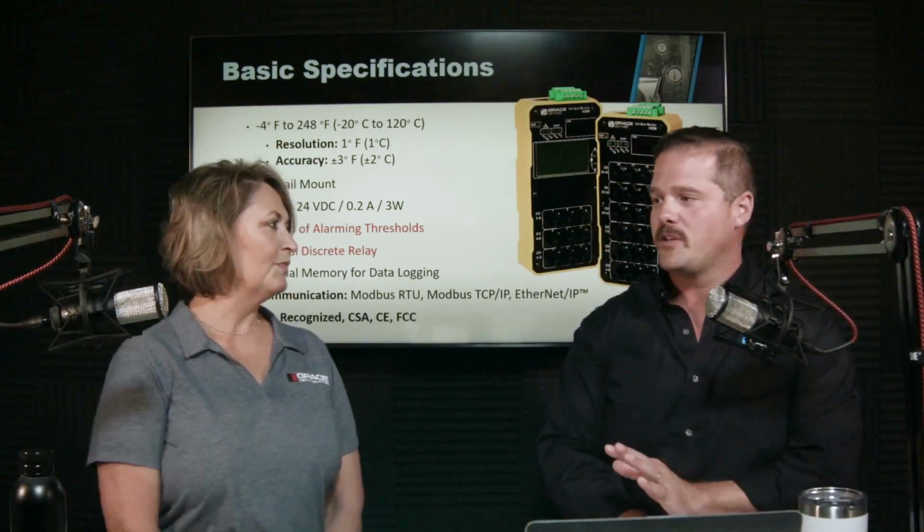I followed up with them, oh my gosh, did the product miss it? He goes, no, Drew, your guys' product performed just as intended. We were able to pull the data log from the charred remains of the switchgear. And sure enough, the data log showed increasing temperatures. If only they would have had the budget to integrate it into their alarming, their SCADA, their building management system, however you get those alarms today, it would have been really, really nice. So now, if they're going to budget for these units, they always make sure that they include an integration plan.